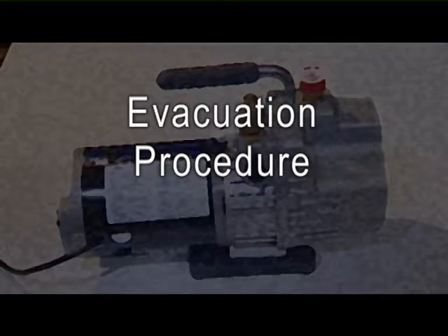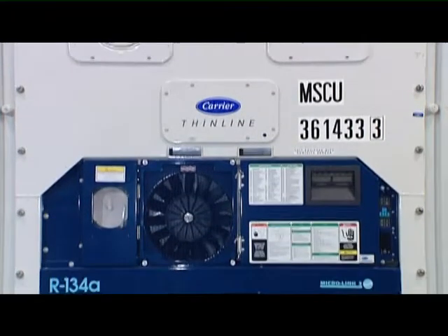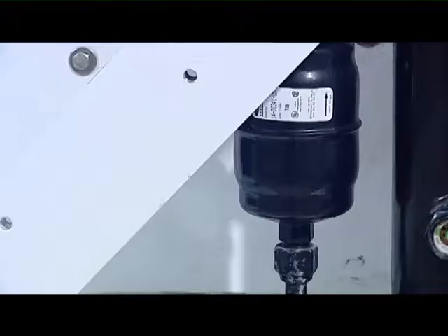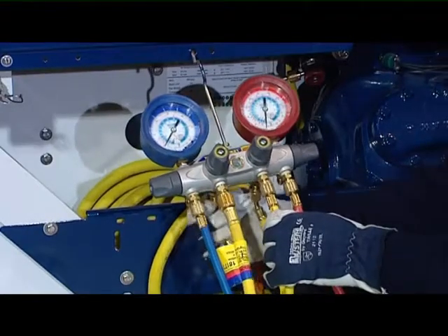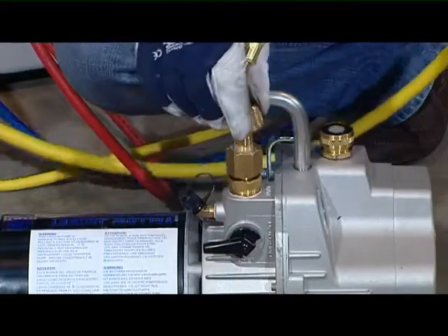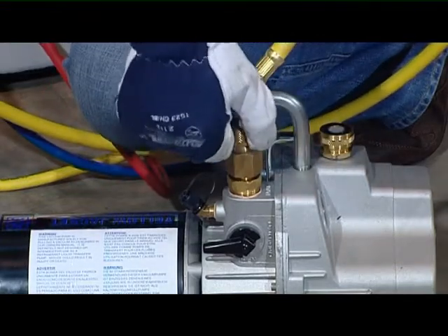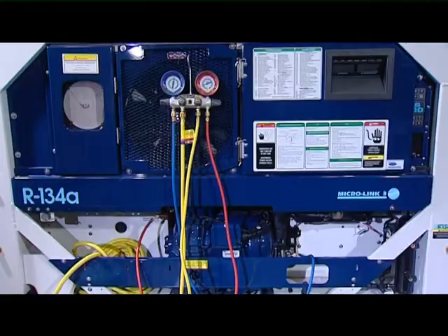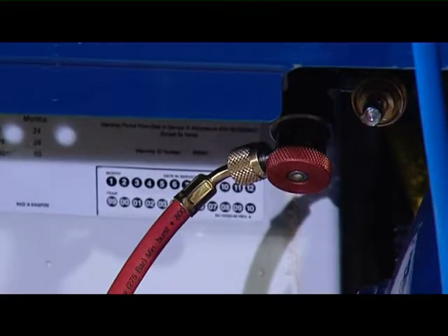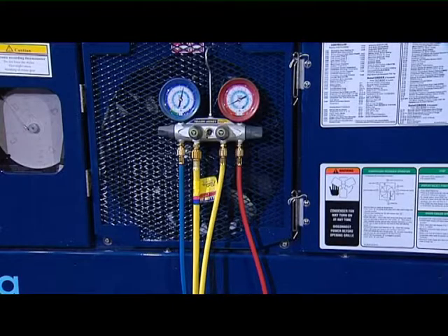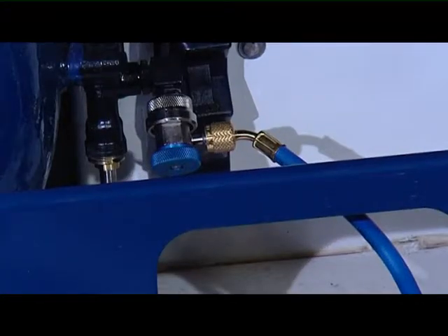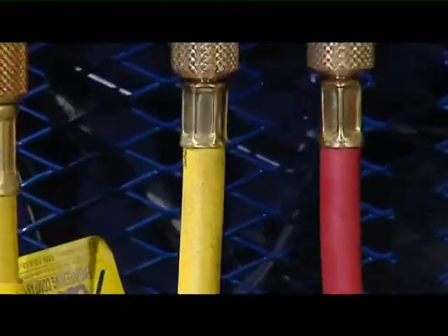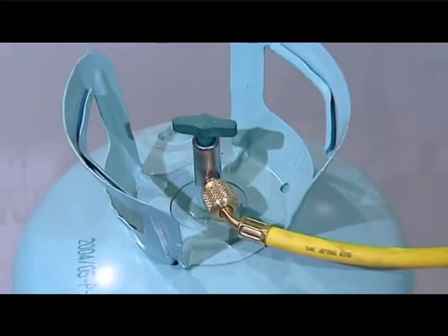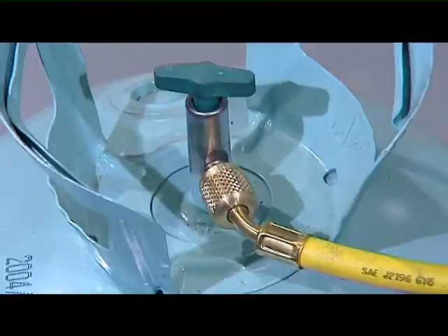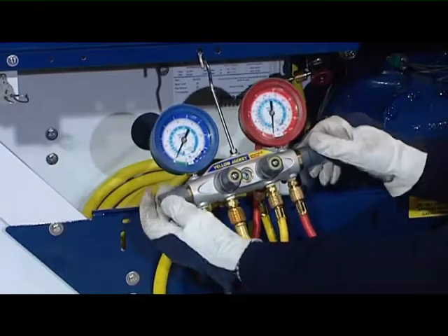Evacuation procedure. Only when the system is empty can you connect the vacuum pump to start to evacuate it. We recommend that you always replace the filter dryer. Connect the large yellow hose to the vacuum pump. Connect the red hose between the high side valve and the discharge side of the system. Connect the blue hose between the low side valve and the suction side of the system. Connect the smaller yellow hose to the refrigerant tank. Open the hand valves on the manifold.